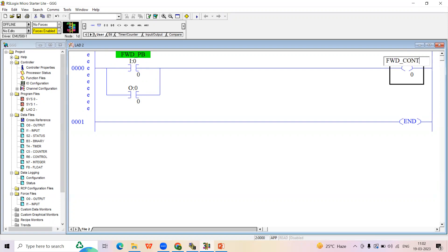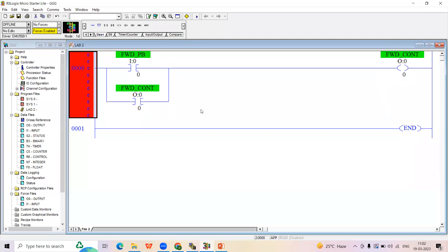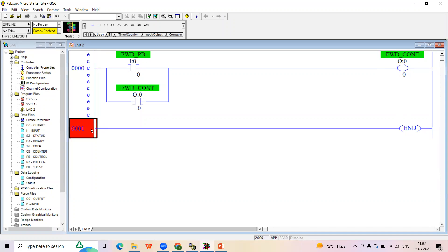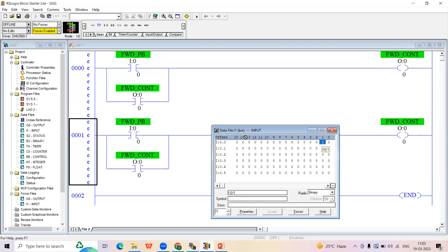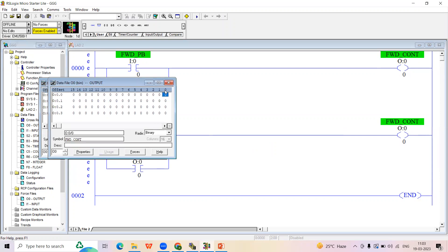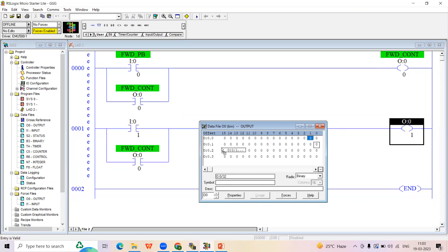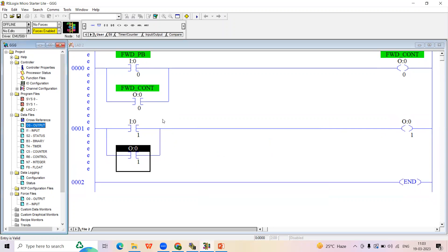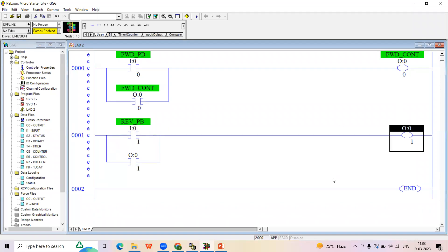Name this the forward push button and the output as forward contactor. Forward contactor is the output. The same logic is required for the reverse as well. You don't have to write it again — simply Ctrl+C and Ctrl+V to copy and paste. Then open the input file, change to the second input address, open the output file for the second output, drag it in, copy the same address for the holding contact, and name it reverse push button with output as reverse contactor.